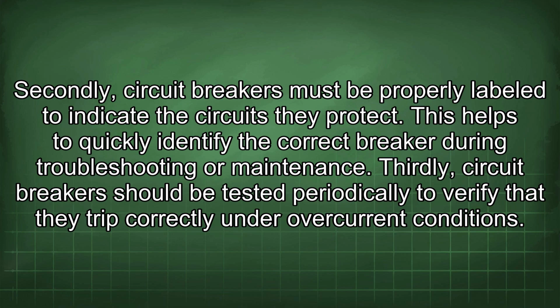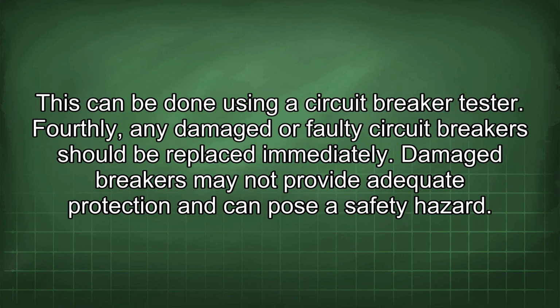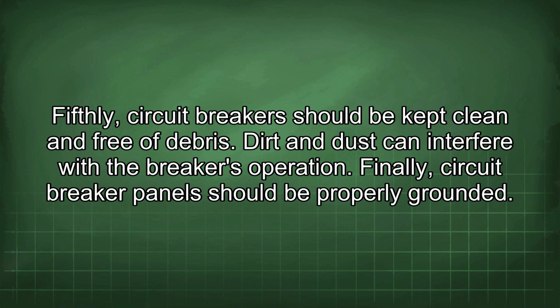Thirdly, circuit breakers should be tested periodically to verify that they trip correctly under overcurrent conditions. This can be done using a circuit breaker tester. Fourthly, any damaged or faulty circuit breakers should be replaced immediately. Damaged breakers may not provide adequate protection and can pose a safety hazard. Fifthly, circuit breakers should be kept clean and free of debris. Dirt and dust can interfere with the breaker's operation.